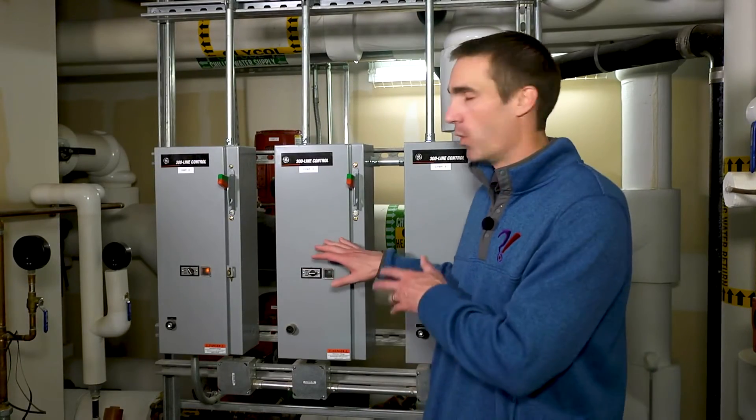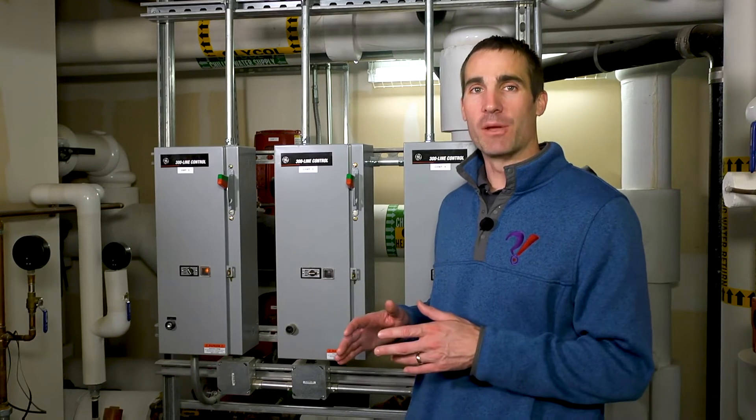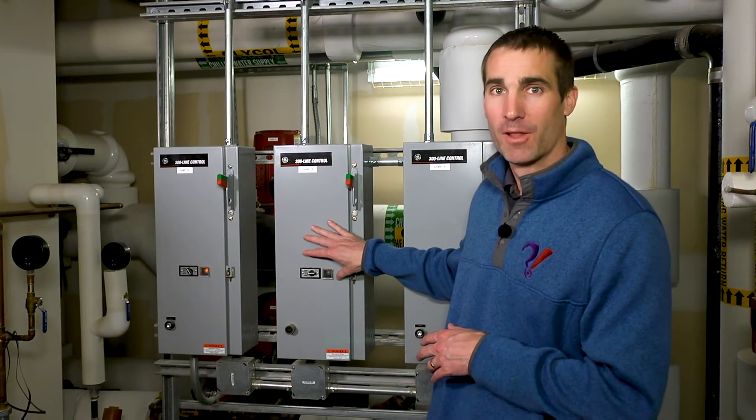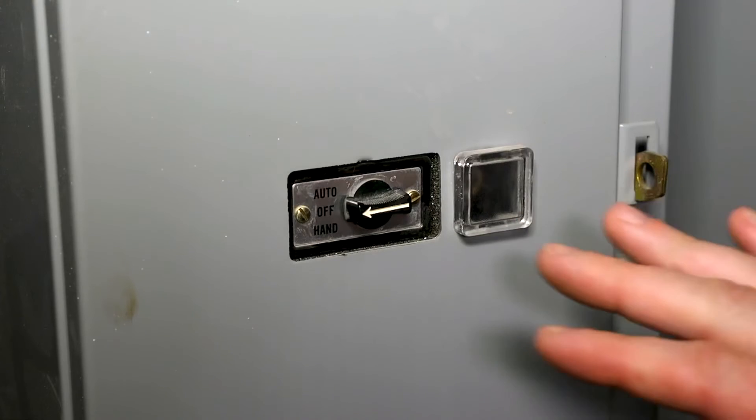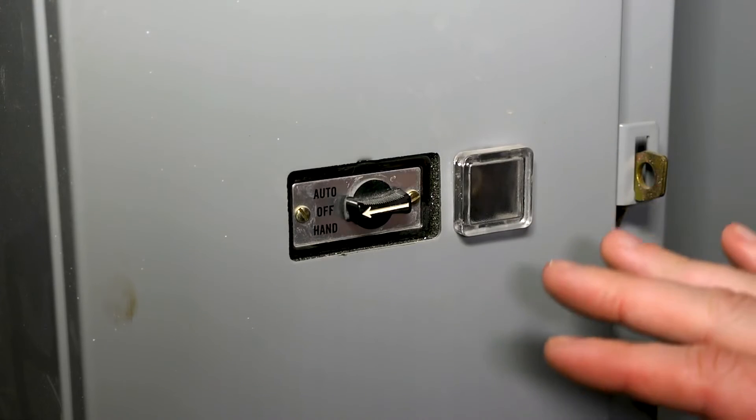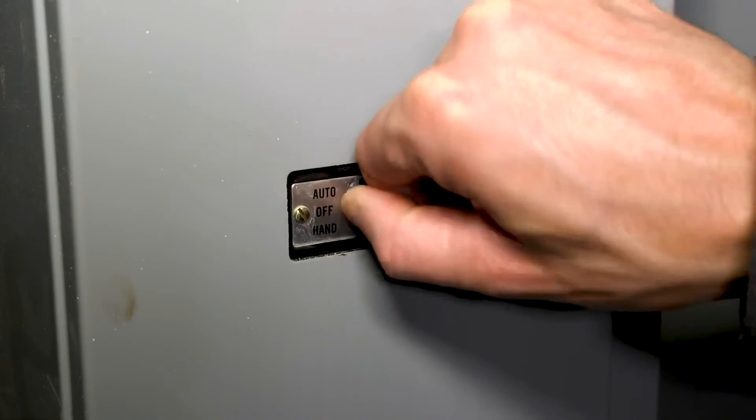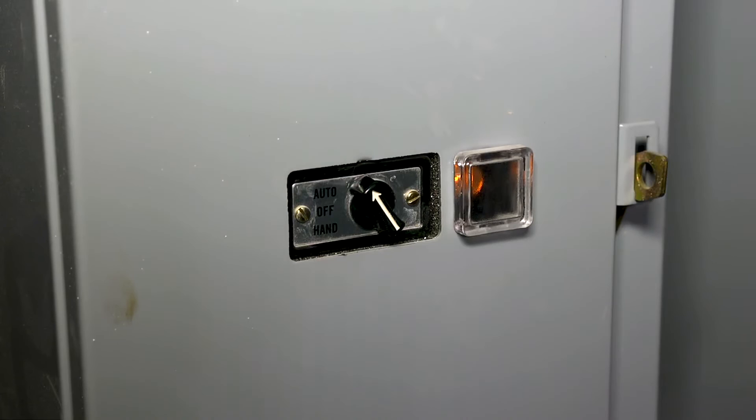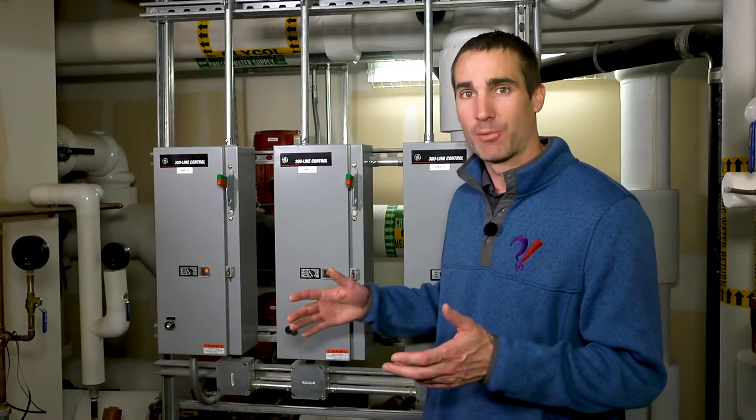Similarly, overrides can occur at the pieces of equipment themselves. Here we have the building automation system trying to enable this particular pump, but at the hand-off-auto switch, it's been overridden off. If we put it back in auto, that allows the building automation system to actually carry out its sequence of operation as intended.